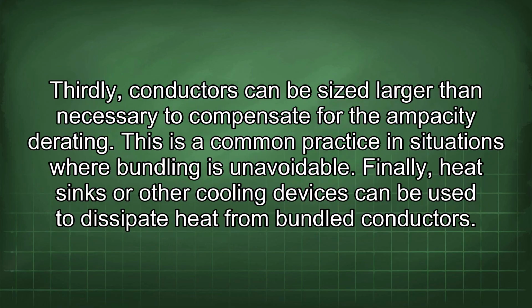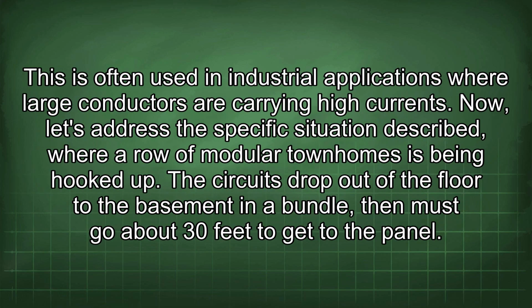Thirdly, conductors can be sized larger than necessary to compensate for the ampacity derating. This is a common practice in situations where bundling is unavoidable. Finally, heat sinks or other cooling devices can be used to dissipate heat from bundled conductors. This is often used in industrial applications where large conductors are carrying high currents.